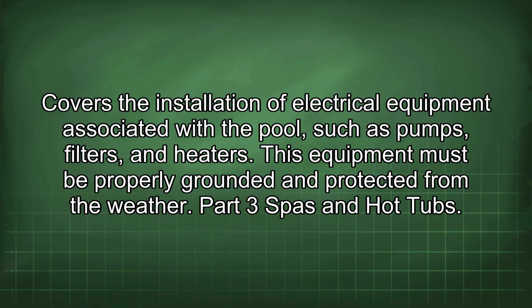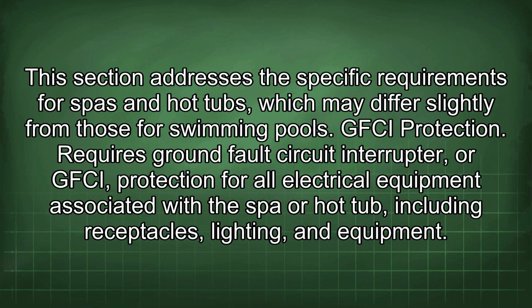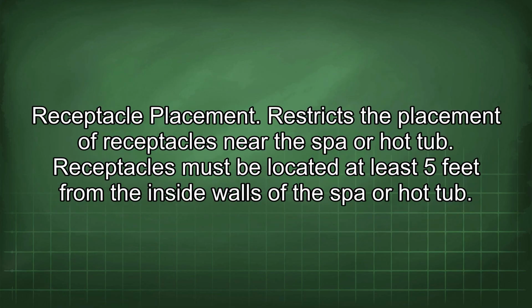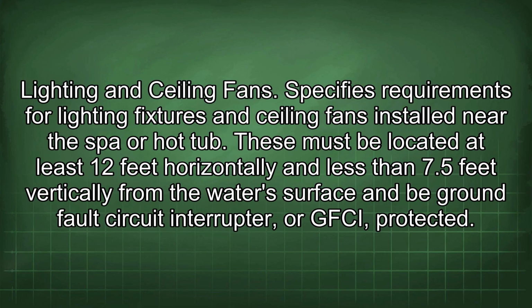Part 3, Spas and hot tubs. This section addresses the specific requirements for spas and hot tubs, which may differ slightly from those for swimming pools. GFCI protection. Requires ground fault circuit interrupter, or GFCI, protection for all electrical equipment associated with the spa or hot tub, including receptacles, lighting, and equipment. Receptacle placement. Restricts the placement of receptacles near the spa or hot tub. Receptacles must be located at least 5 feet from the inside walls of the spa or hot tub. Lighting and ceiling fans. Specifies requirements for lighting fixtures and ceiling fans installed near the spa or hot tub.